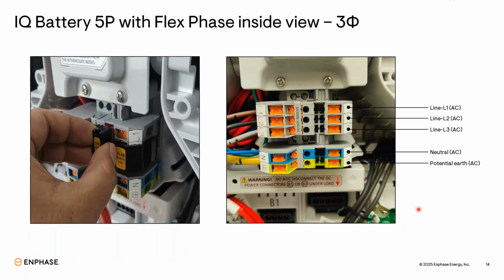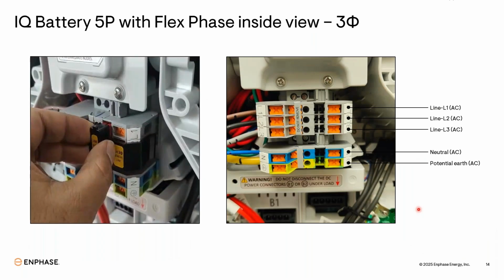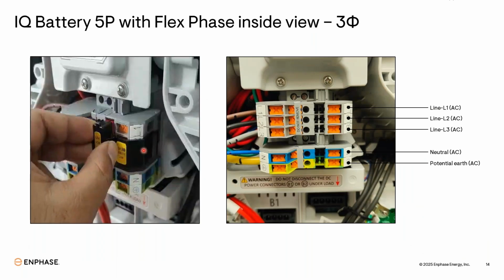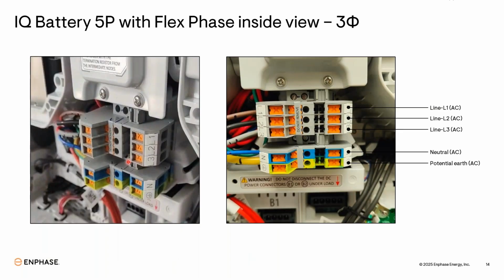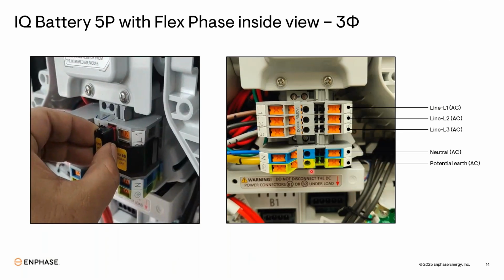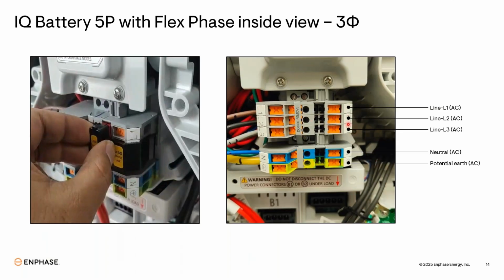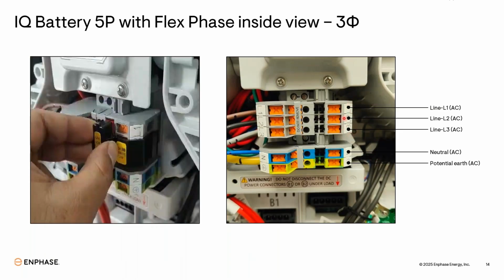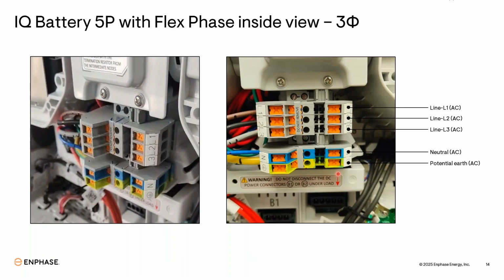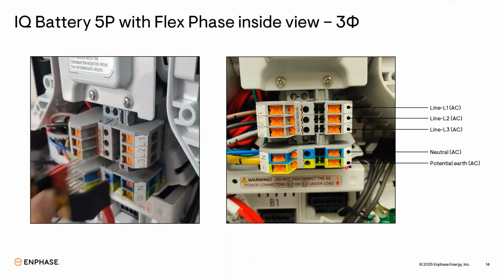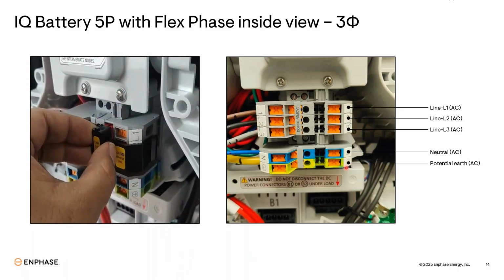And if you want a three-phase connection, you simply need to remove this link. You just need to remove this link, and you will see L1, L2, L3 in front of you. So you just need to connect these L1, L2, L3, neutral, earthing. So these are your three-phase connections.